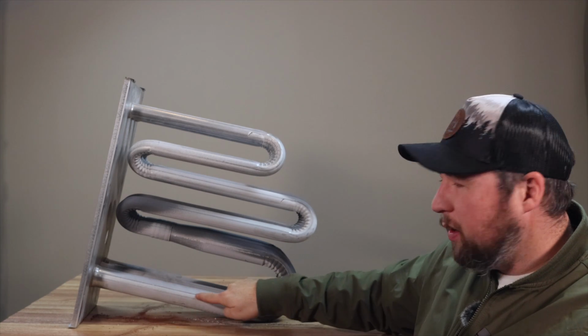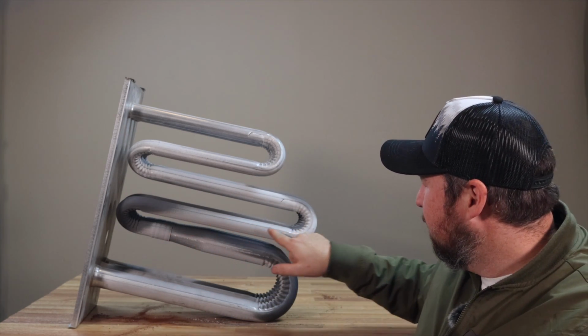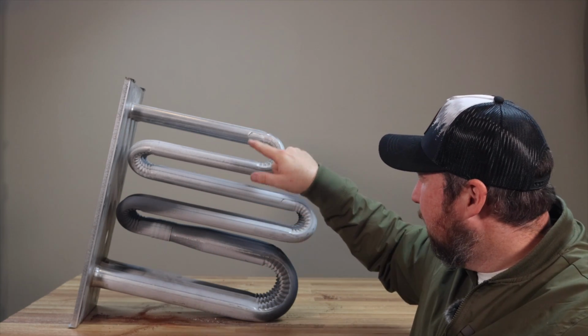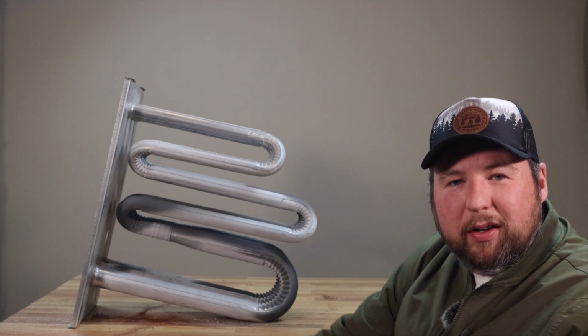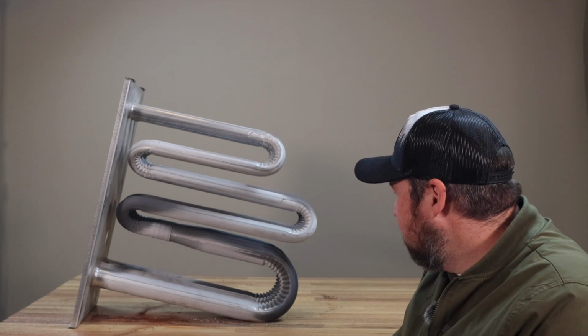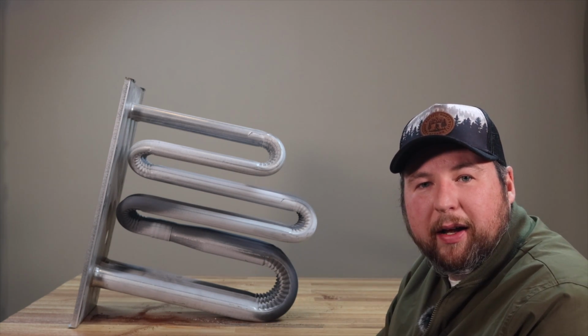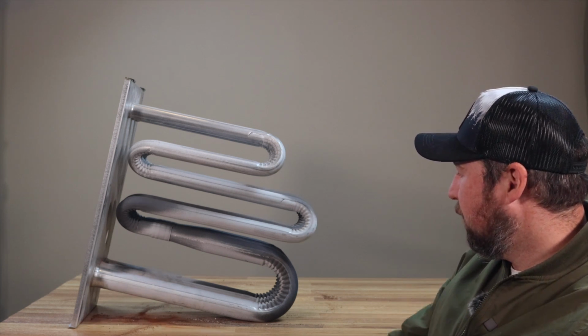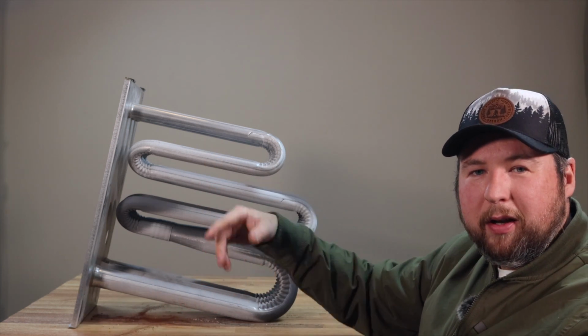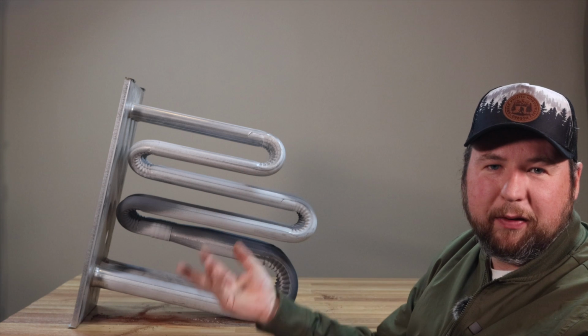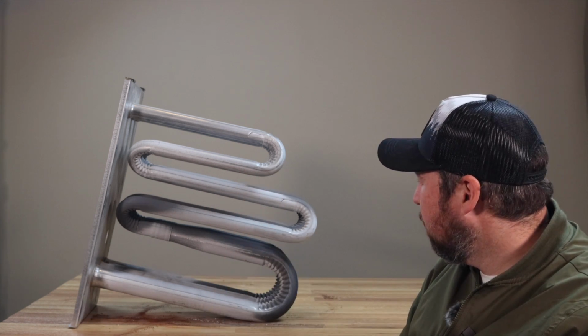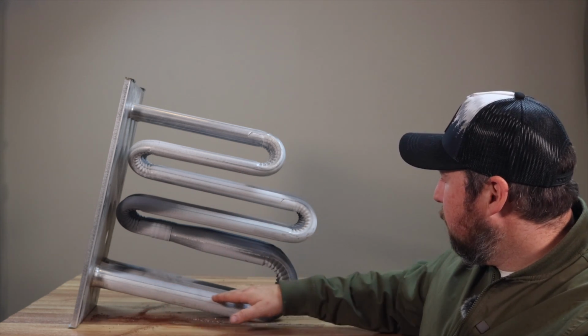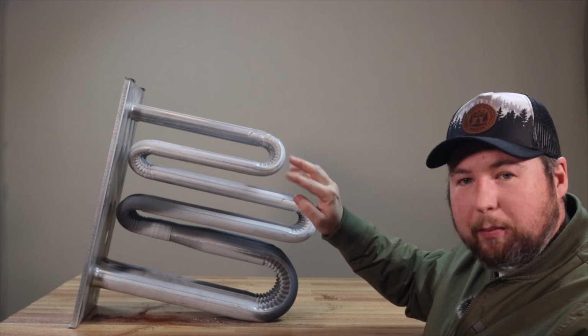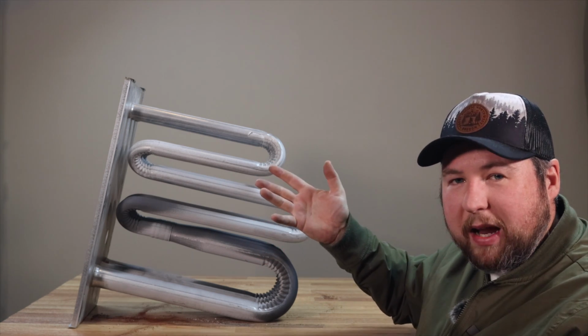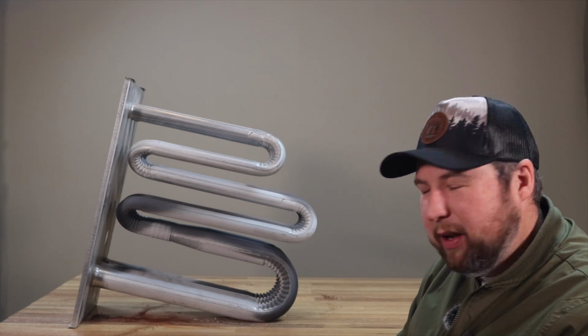But you can see here it does still kind of keep that snake-like shape, right? And that's because it's a coil, you know. We want to use that to maximize our surface area. Because if we just had one massive tube, and you have all that air, it's not touching a lot of it, so you're not going to be maximizing your heat transfer. Now, all of them pretty much look like this, but some of them have little differences depending on the manufacturer. They do little things to maximize heat transfer.